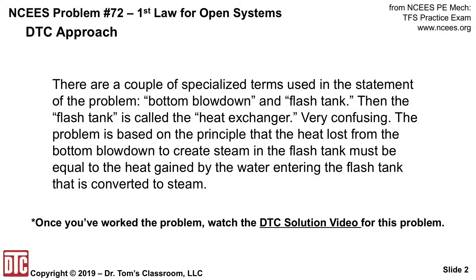There are a couple of specialized terms used in the statement of the problem: something called bottom blowdown and flash tank. The flash tank is also called the heat exchanger — very confusing. The problem is based on the principle that the heat loss from the bottom blowdown to create steam in the flash tank must be equal to the heat gained by the water entering the flash tank that is converted to steam. That's the basis of most every heat exchanger.